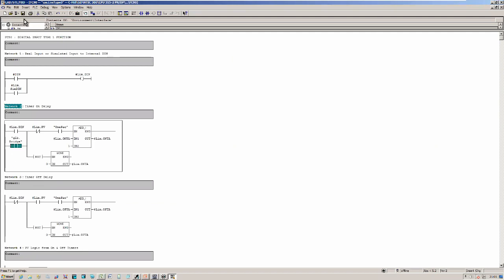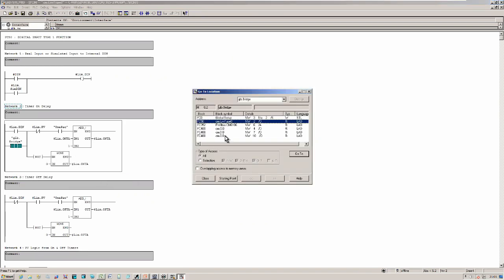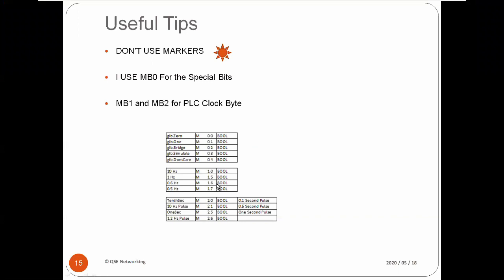But now, in my program, if I save it, I can search everywhere where we bridged it. We can see anywhere in the program where somebody at night maybe had a problem and had to bridge something. And we can see what's happened here. Somebody's gone and done a bridge here. So what is going on? Maybe this is me originally, there was supposed to be an extra bit there, but at least we know there's something missing. Whereas if you've just got a link, you don't know where to find it, and you have issues when trying to debug software.